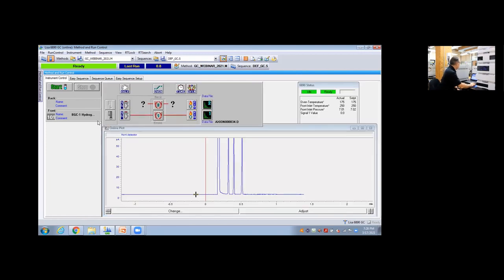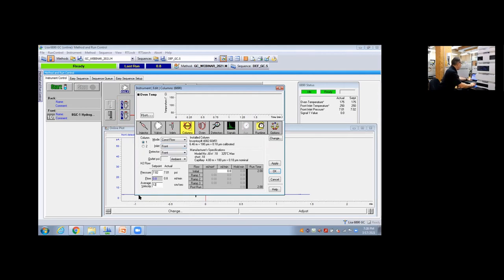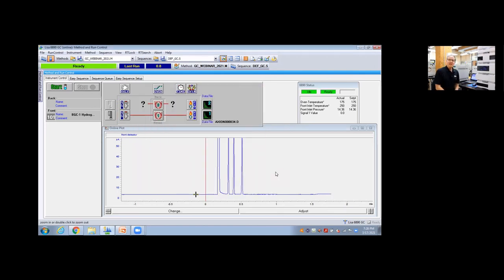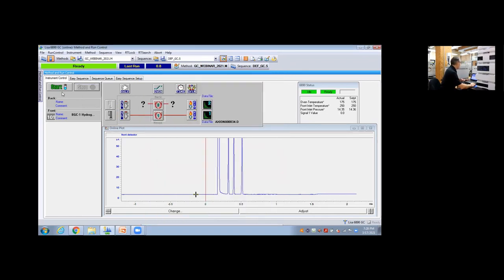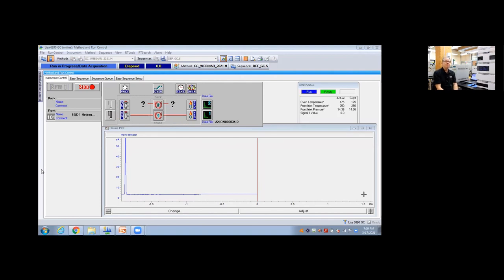So dare we be bold enough to go one step further? Sure. Why not? I don't know. 128. I tried to keep the math simple. So can we do it? Yeah, we need 14 PSI to do that. How much pressure does the GC have to work with? You got about a hundred PSI. Most GCs go up to a hundred. I don't really like running them up near a hundred. That's where you'll find all your leaks. Typically we're running more around 10 or 20 PSI. But again, the beauty here running hydrogen is that we can run at extremely high linear velocities, 128 centimeters per second and still operate, still be using reasonable pressures on the inlet. And let's see what this one looks like. So anyone want to predict the analysis time? The last peak will come off. Yeah, it should be half the time before. So the last one was 0.51. So about 0.25, 0.26 should be our last peak.